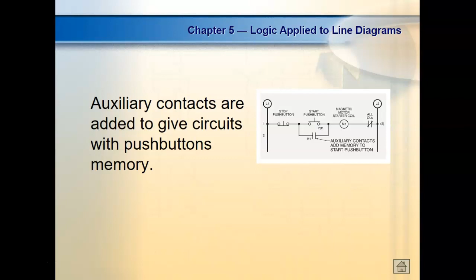A common start-stop control circuit is created by adding the NOT logic of a stop push button to the memory logic. Let me simplify this. This is a very typical setup for a start-stop circuit. We don't want anything stopped unless we push the button to stop it, but once we start it, we want it to seal in and keep it running until we tell it to stop. Does that make sense? It's using memory as well as NOT logic to keep your circuit energized.